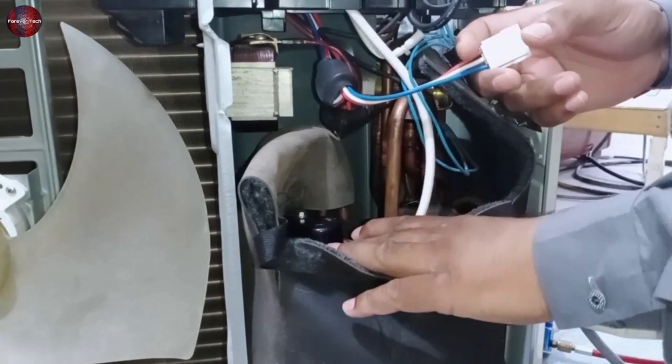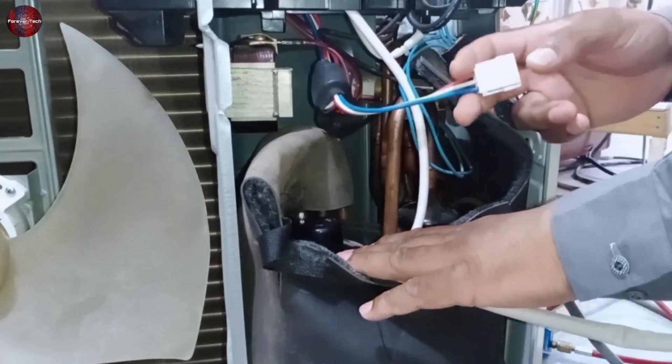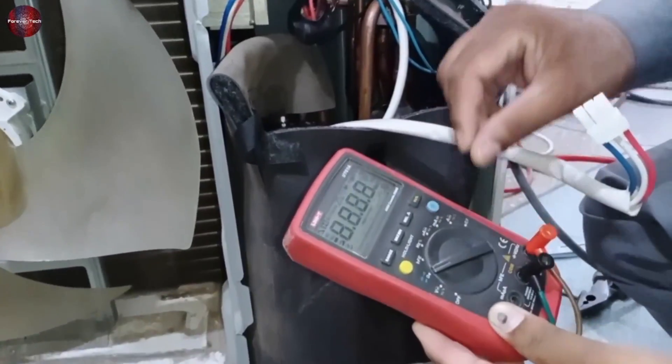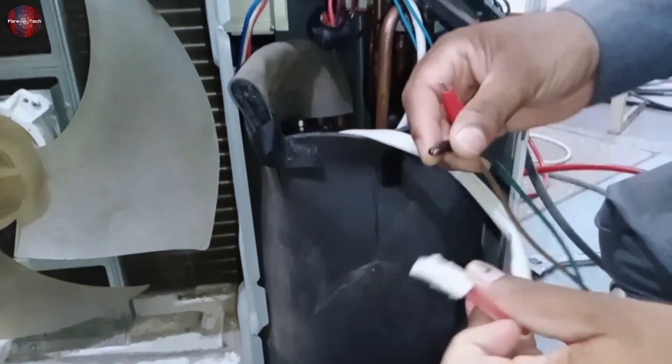And this test will be done after separating the compressor from the PCB. The compressor could not be tested with the PCB attached. Take a multimeter and set it to ohms. After this, attach the probes of the multimeter to compressor terminals.